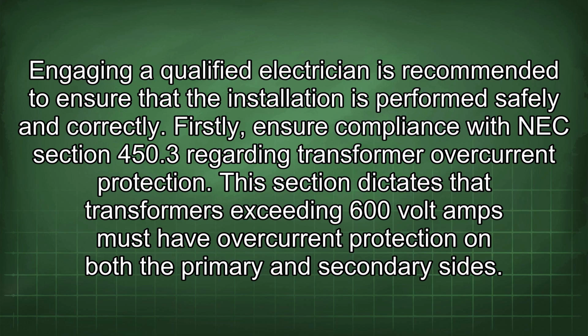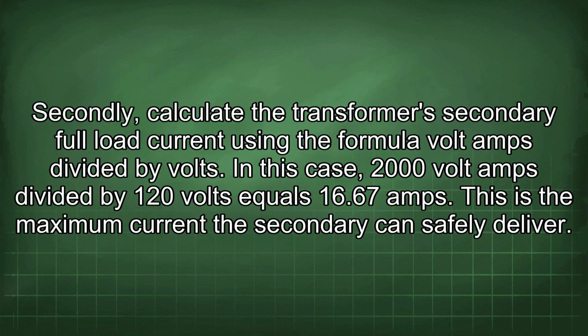Firstly, ensure compliance with NEC Section 450.3 regarding transformer overcurrent protection. This section dictates that transformers exceeding 600 volt amps must have overcurrent protection on both the primary and secondary sides. Secondly, calculate the transformer secondary full load current using the formula volt amps divided by volts. In this case, 2000 volt amps divided by 120 volts equals 16.67 amps. This is the maximum current the secondary can safely deliver.